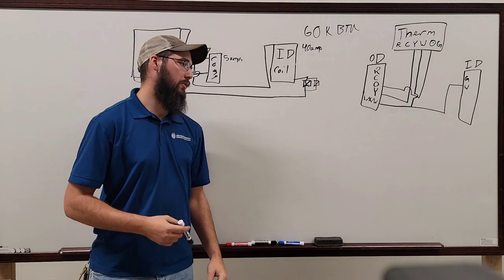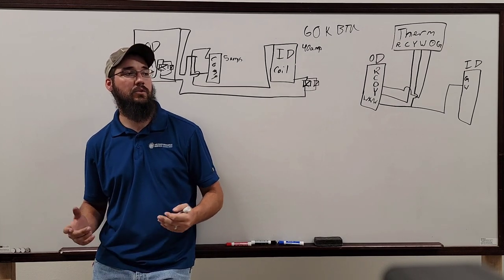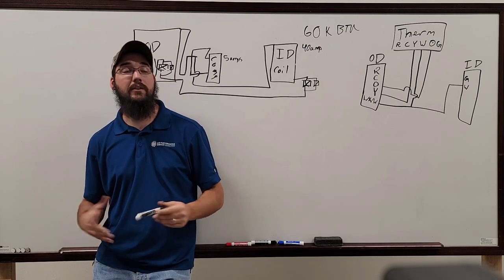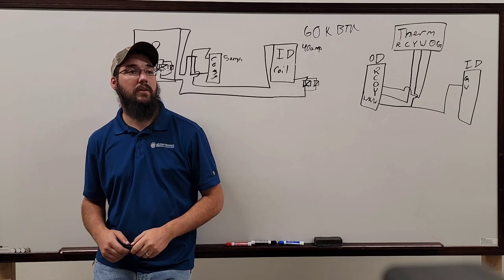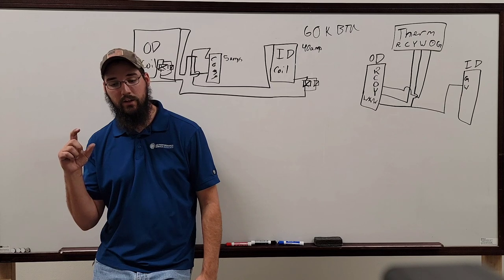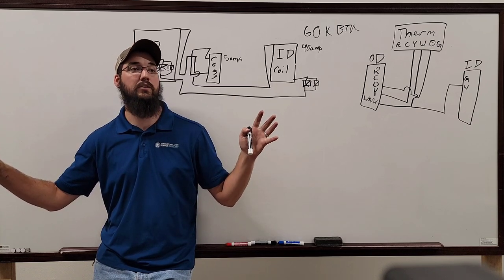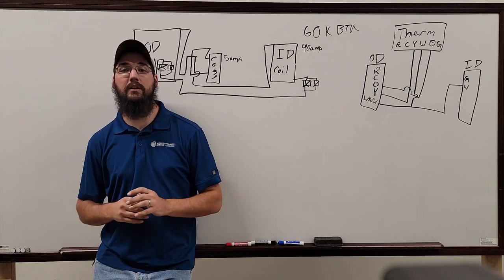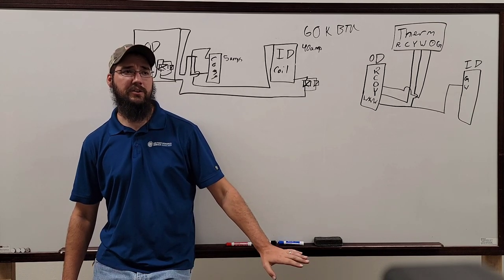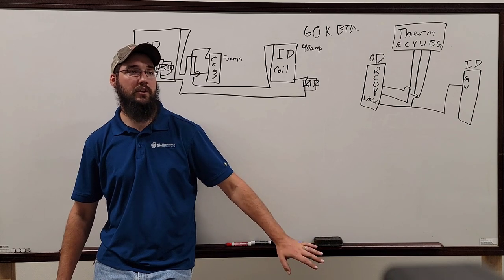So, now we'll hit on that real quick. Mini splits and VRVs are really changing the game when it comes to heat pump systems, and that's why most of the time they don't come with any kind of auxiliary heat, because of their ability to control refrigerant flow through EXVs and by ramping not only the compressor speed, but also both indoor and outdoor fan speeds. They have an extremely unique ability that they'll run down way further than any standard split. Their bottom end of operation, instead of being in the 20s, is down closer to zero before they become too inefficient to operate and lock out.